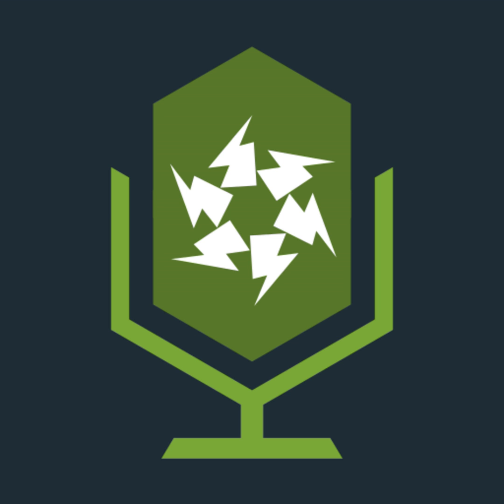Now, if you imagine being in a hospital and you're stuck there on the bed or whatever, and then there's something shoved up the, imagine if the power goes out, and if the loss of power is going to result in danger for yourself, then we would consider this a group 2 location. So failure of the supply can cause danger to life.